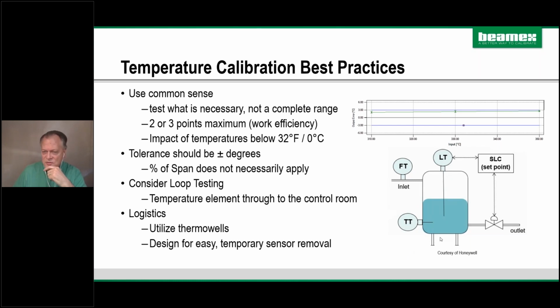I've also seen installations where the temperature transmitter is mounted up inside the bottom of the tank, and you only have a few feet in there, so you have to shimmy in on your back, pull the probe out, and then pull the dry block up underneath to get it into position to make a test.